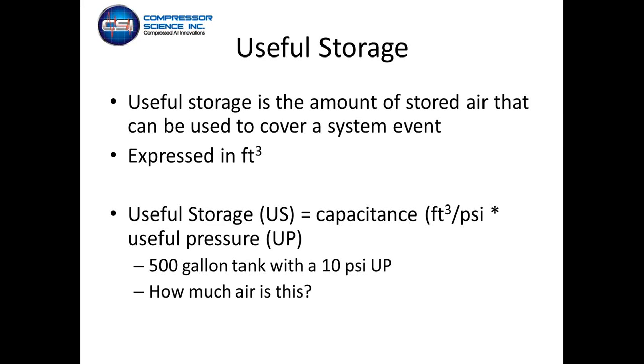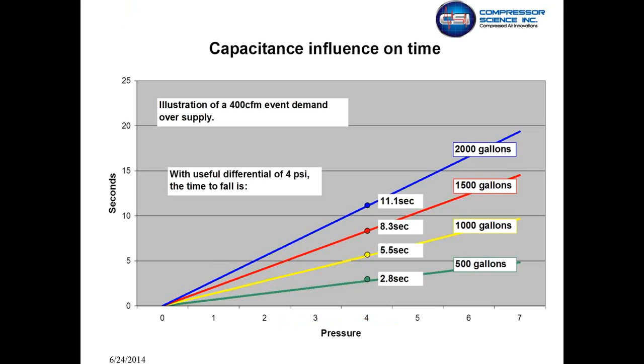And useful storage is the amount of stored air you can use to cover a system event, expressed in cubic feet. If you have a specific event that's going off and you can apply storage to it, so we know exactly how many cubic feet per PSI we need, let's say a 500-gallon tank with a 10 PSI useful pressure, we'd be looking at 46 cubic feet to deal with that specific capacitance for useful storage. Obviously, you can't size a compressor storage tank to deal with having a compressor off. You'd be talking about a huge tank when you get into over 100 horsepower.